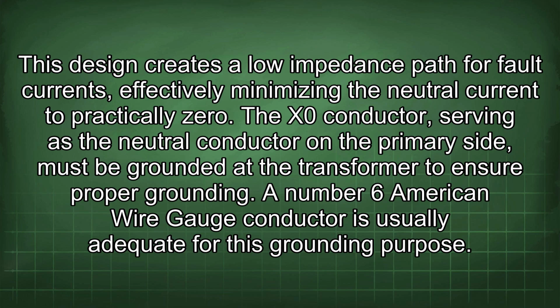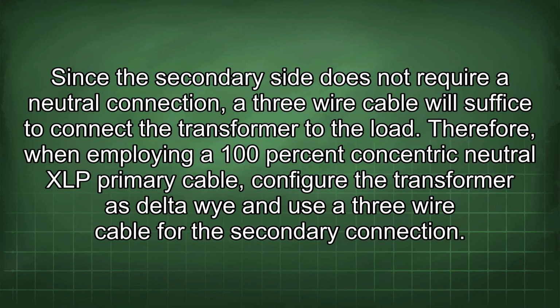The X0 conductor, serving as the neutral conductor on the primary side, must be grounded at the transformer to ensure proper grounding. A number 6 American wire gauge conductor is usually adequate for this grounding purpose. Since the secondary side does not require a neutral connection, a 3-wire cable will suffice to connect the transformer to the load. Therefore, when employing a 100% concentric neutral XLP primary cable, configure the transformer as Delta-Wye and use the 3-wire cable for the secondary connection.